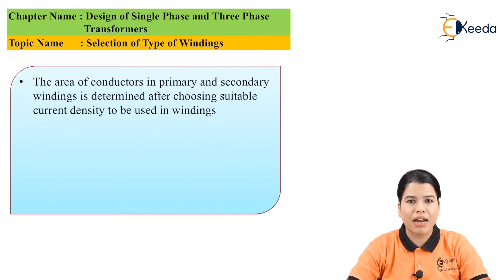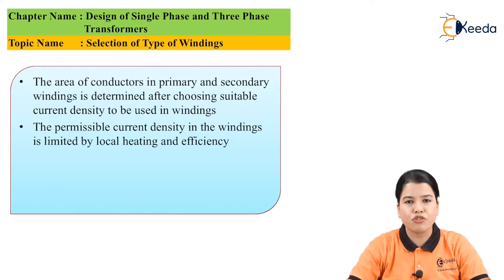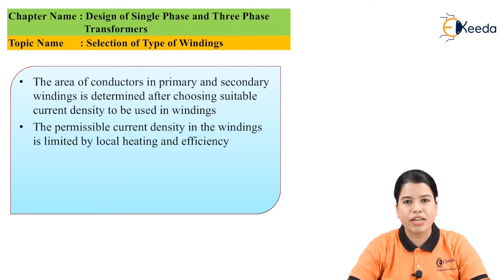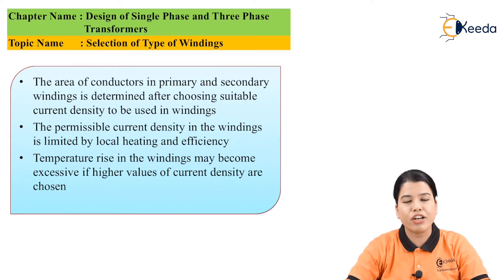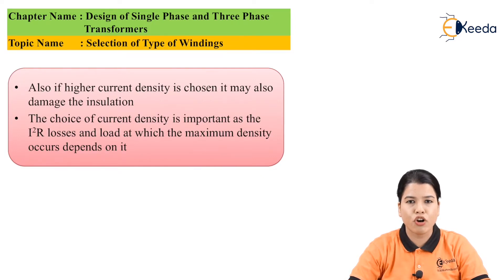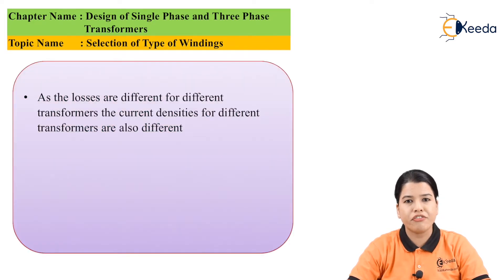The area of the conductor of the primary and secondary winding mainly depends upon the value of current density. The permissible current density of the winding should be selected depending upon the value of current. This current density will also affect the losses as well as the rise in temperature. If a higher value of current density is chosen, the temperature rise in the winding will be very high, and it can damage the insulation. Also, the I²R losses depend upon the value of current density. Since losses differ across transformers, the current density values will vary from one transformer to another.